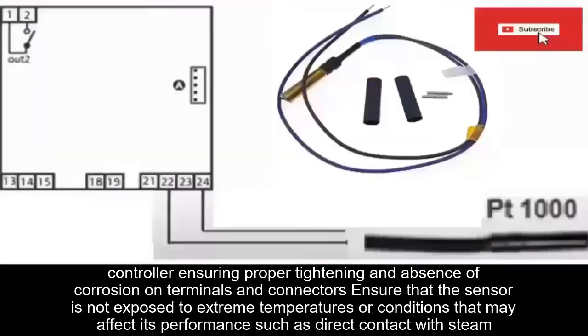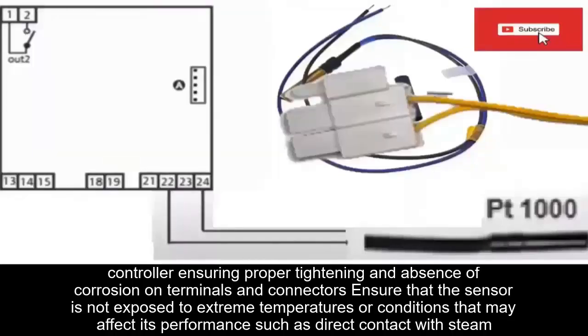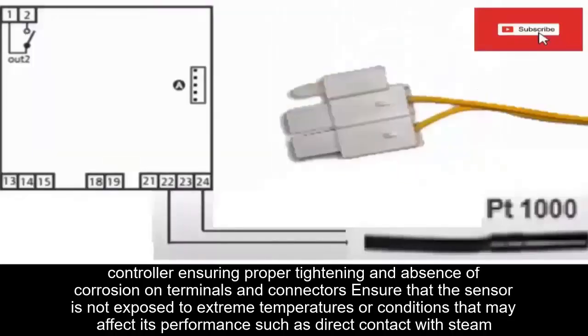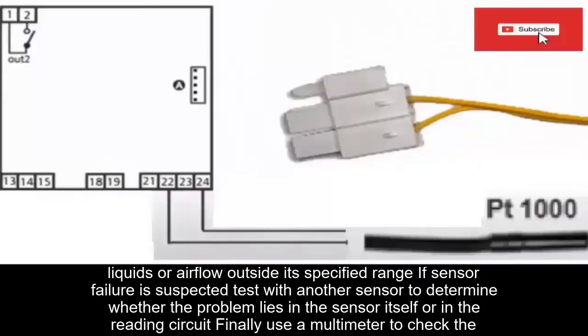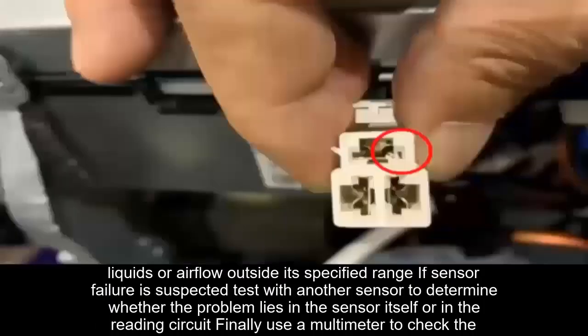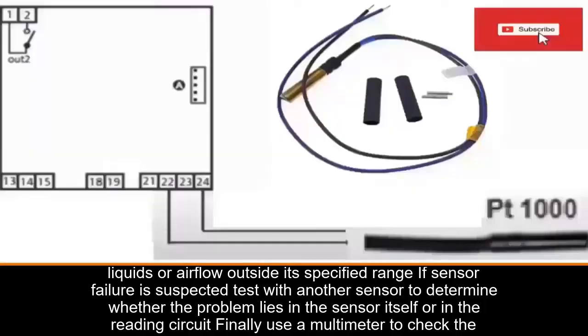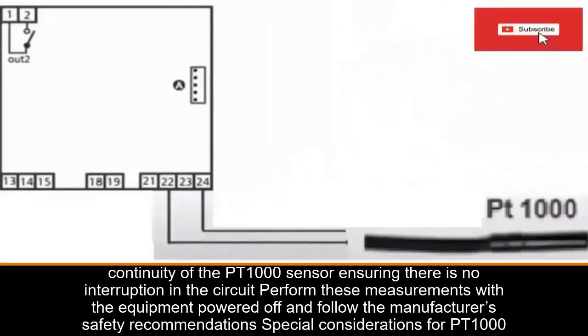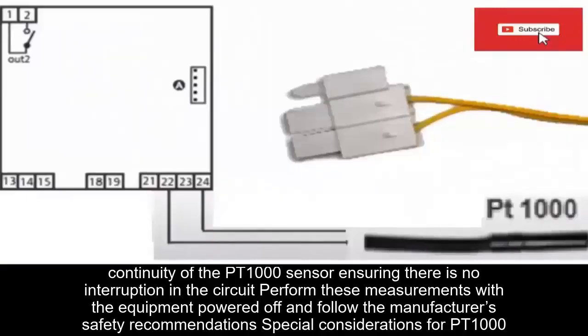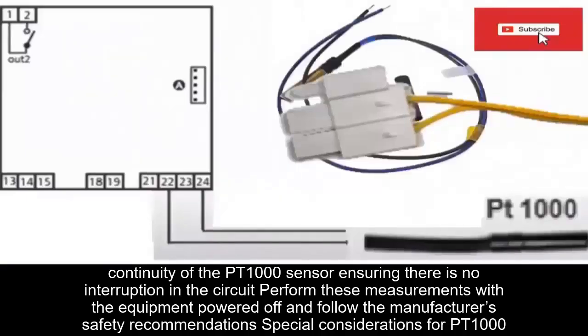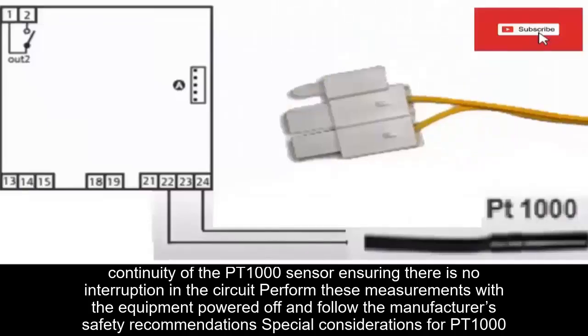Ensure that the sensor is not exposed to extreme temperatures or conditions that may affect its performance, such as direct contact with steam, liquids, or airflow outside its specified range. If sensor failure is suspected, test with another sensor to determine whether the problem lies in the sensor itself or in the reading circuit. Finally, use a multimeter to check the continuity of the PT1000 sensor, ensuring there is no interruption in the circuit. Perform these measurements with the equipment powered off and follow the manufacturer's safety recommendations.